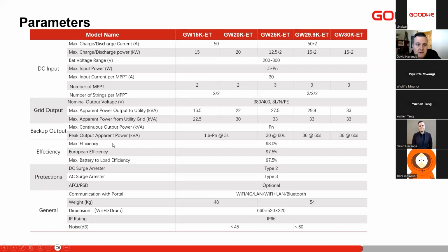So just looking at the parameters of the ET15 to 30. We have essentially 4 models, the 15 kilowatt, the 20 kilowatt, the 25 and the 30 kilowatt. You'll see the 29.9, that's mainly for Europe, for regulation wise. The 15 and the 20 both have 2 MPPTs and they both have 1 battery input. The 25 and the 30 have 3 MPPTs and dual battery input, so 2 battery inputs. These are also high voltage batteries on these inverters.